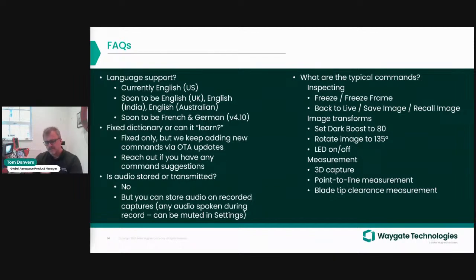And yes, if you're doing inspections where frequent, repetitive measurements are required, then there's a huge opportunity to save a lot of time. Also, from a human factors point of view, sometimes you can press the wrong buttons because you're not concentrating so much if you're doing it repetitively. By just saying point-to-line measurement or blade tip clearance, and all of the other measurement types are supported, if you've got a 3D PM tip fitted. If you haven't, if it's a stereo tip for instance, you would need to select what tip is fitted first, and then those measurement commands would work.